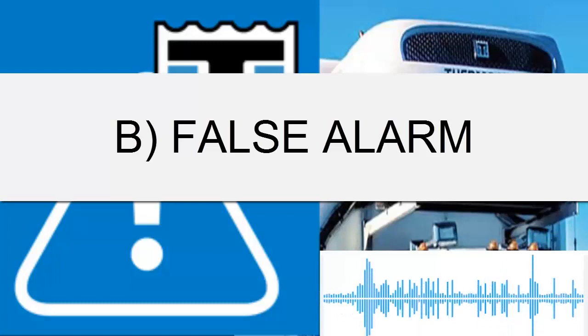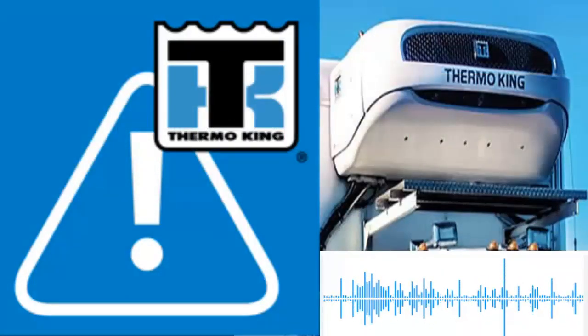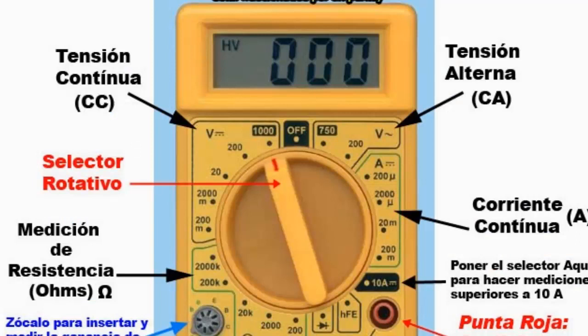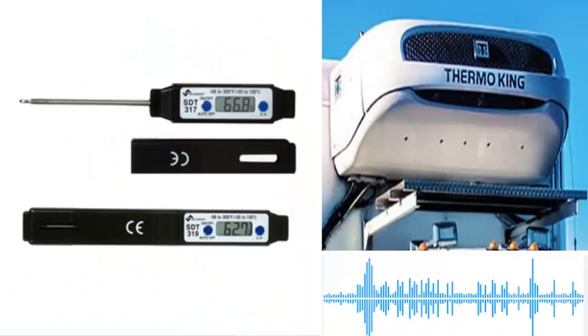Now let's look at some measures when the alarm is false. 1. Sometimes problems with sensors, their incorrect placement, or issues with cables can trigger false alarms. 2. Check the location of the temperature sensors and ensure they are correctly connected. It may be helpful to measure the electrical resistance of the sensors with a digital multimeter. 3. If your equipment uses PT1000 sensors, verify if they are calibrated correctly to have a resistance of 1000 ohms at 0 degrees Celsius. 4. Use independent digital thermometers to see the true temperature values.